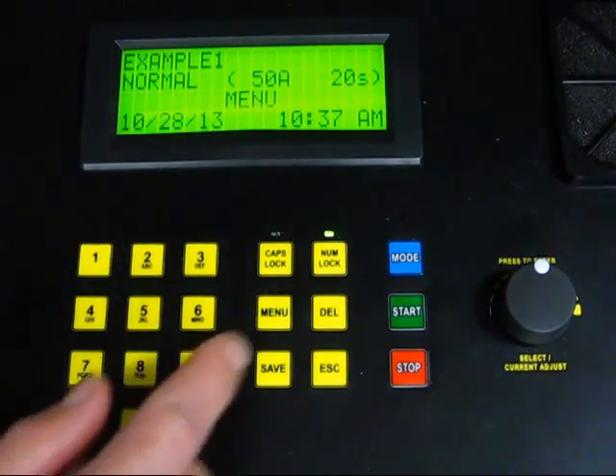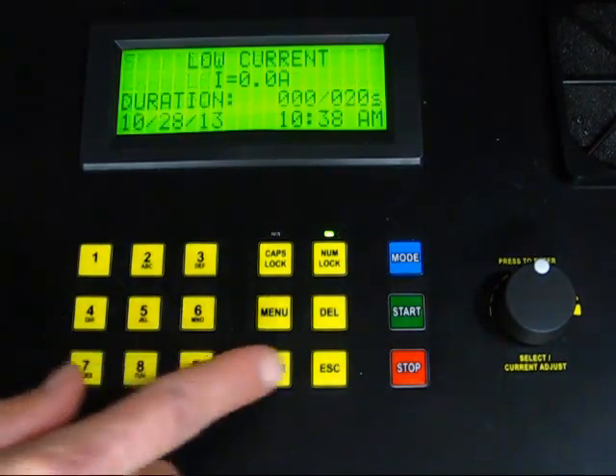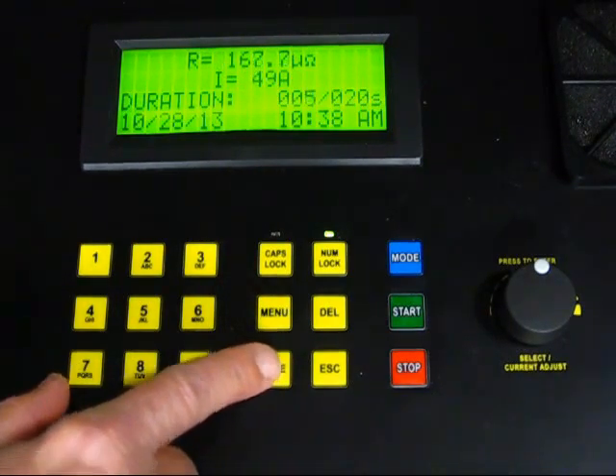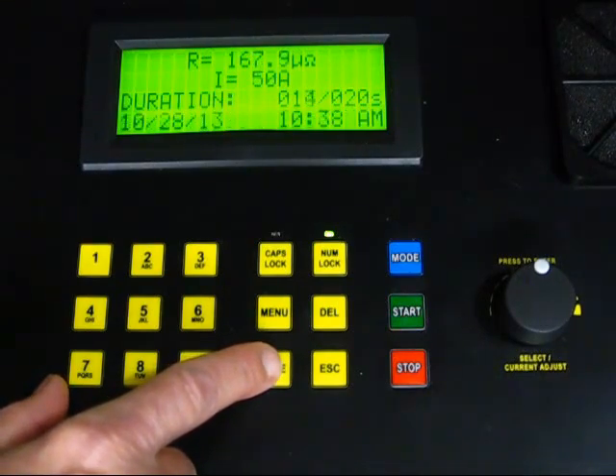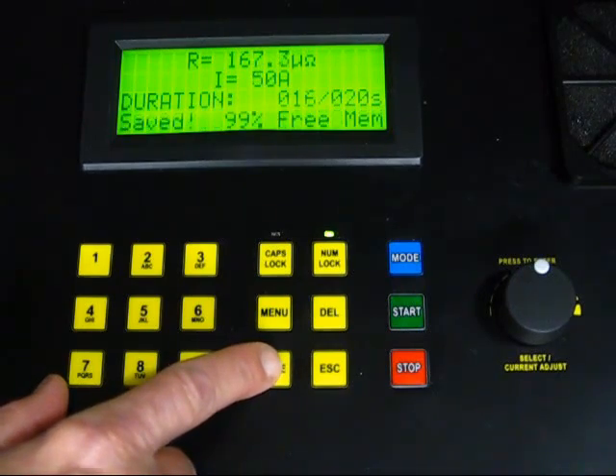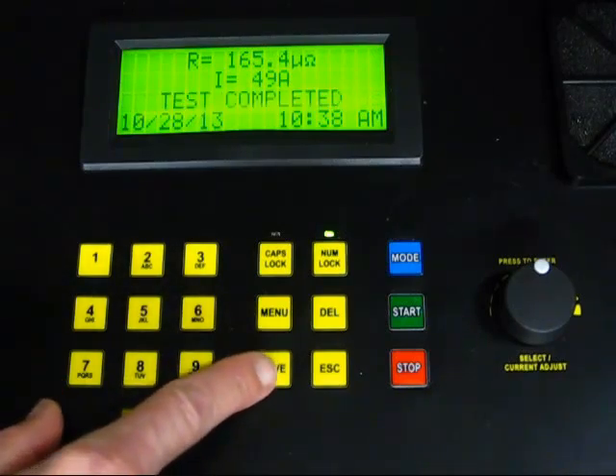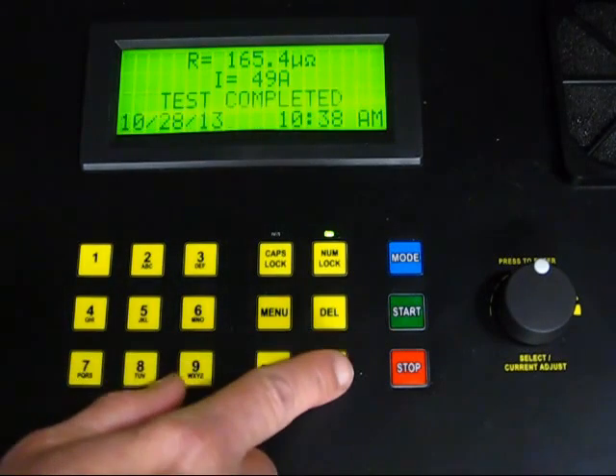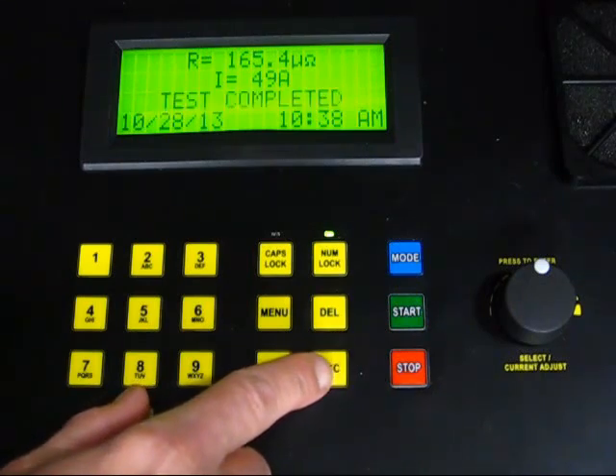To begin the test, press the green Start button. After a few moments, the LCD display indicates the test is underway. A feature of the Model 6292 is the ability to save partial test results. To do this, we will press the Save button every 5 seconds during the test. This allows us to save partial measurements at 5, 10, and 15 seconds, as well as the complete measurement at 20 seconds. All these measurements will be stored in a test record within the object we have named Example 1. When the test is finished, the message Test Complete appears blinking on the screen. Press Save to store the test in the Model 6292's memory. We will then press the Escape button to return to the main screen.